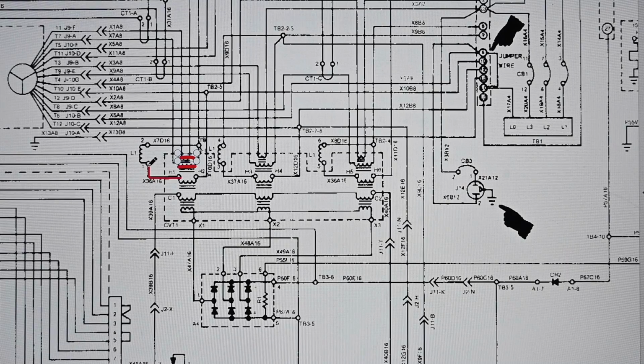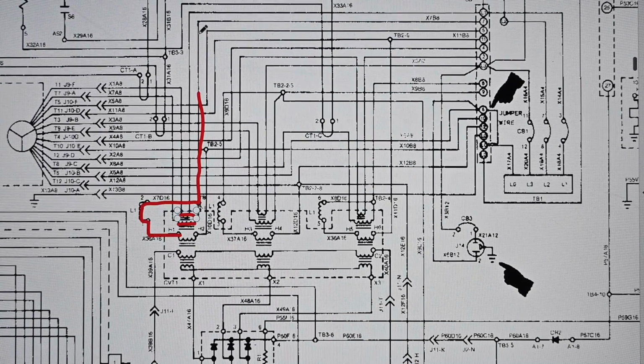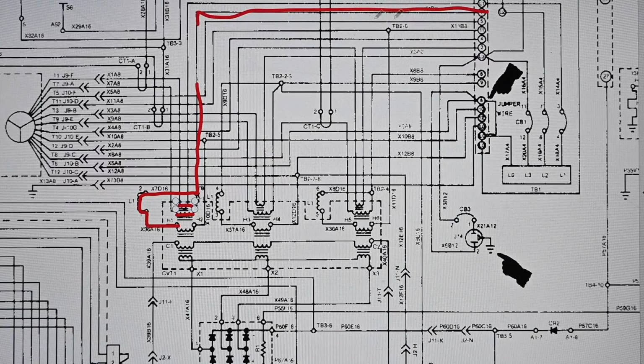One side of that winding comes over here, through inductor L1, comes over here, then comes up. If we follow this wire all the way up, it comes up here and ultimately goes over to this reconnection switch, being reconnected into another winding, or coming out of the stator ultimately. If we look at the other side of this winding, it comes up, makes a connection right here, and goes over to the stator. That's happening with this winding and also with this winding right here. Each of those is ultimately being connected across a pair of the wires coming out of the stator, so these windings are just getting a constant voltage on them from the generator.